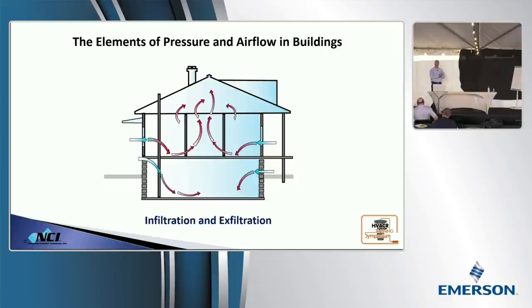Now, we understand how these apply to comfort issues. John explained to us yesterday how they apply to IAQ issues. Now, let's talk about how they apply to combustion air. If you have infiltration, what's combustion air doing? Think of the first two letters, in. Combustion air is going in through infiltration. If you have exfiltration, what's combustion air doing? Think of the first two letters and then add IT to it. Exit. It's leaving the building.